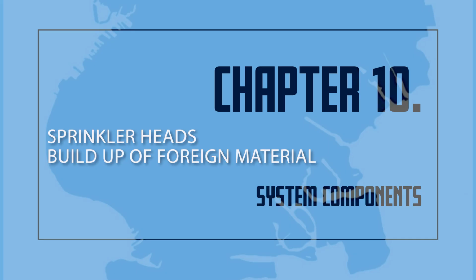Replace loaded sprinkler heads with new sprinkler heads rather than attempting to clean them. If the deposits are hard, attempts to clean the heads are likely to damage them. This damage may prevent the sprinkler heads from working properly. The damage may also cause the sprinkler head to leak.